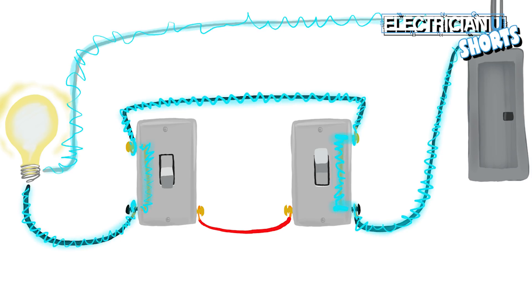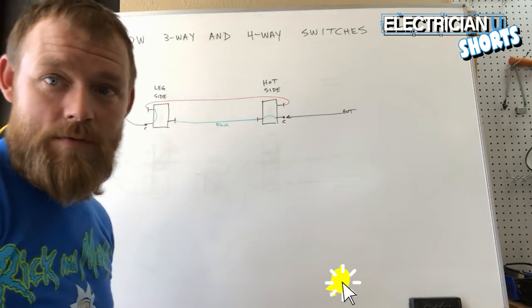And if you're back on this side and you wanted to change the switch so that the light goes off you just change this one and it connects the common to this traveler. So you have power that goes through and stops. It has no way of getting over to the light. That's pretty much it. That's the simplest explanation I have for how a three-way switch works.